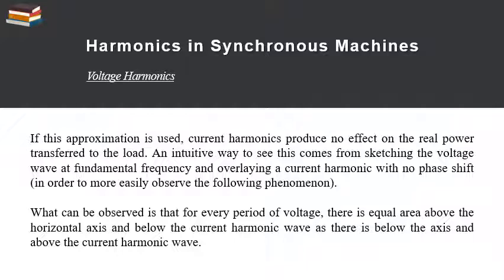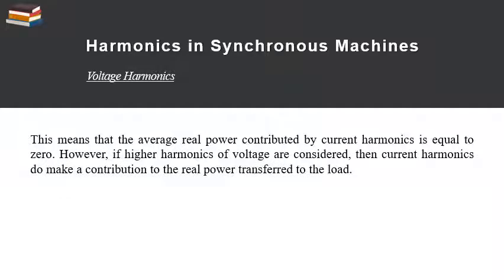What can be observed is that for every period of voltage, there is equal area above the horizontal axis and below the current harmonics waves as there is below the axis and above the current harmonics waves. This means that the average real power contributed by current harmonics is equal to 0. However, if higher harmonics of the voltage are considered, then current harmonics do make a contribution to the real power transferred to the load.